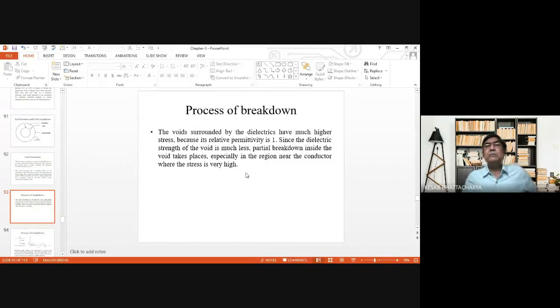Therefore, the stress immediately becomes almost negligible. And if the stress becomes negligible, the positive ions and electrons formed due to arcing or flashover start recombining. After some time, the void again gets its dielectric strength back. But by this time, the supply voltage is not held at its previous value, but since the operating voltage is AC, it goes on increasing, and after some time, the voltage across the bubble or the void may be such that the resulting stress may again cause another break.